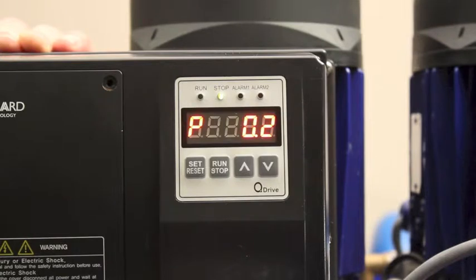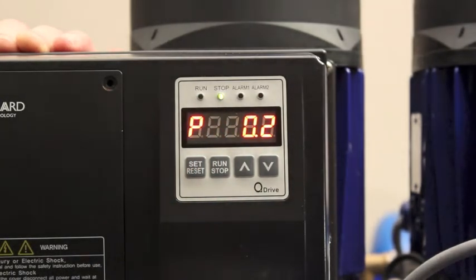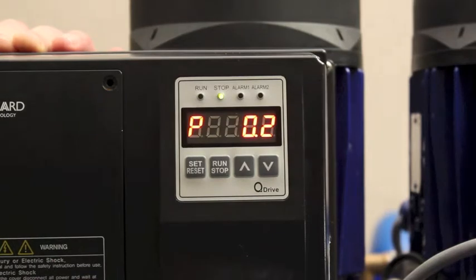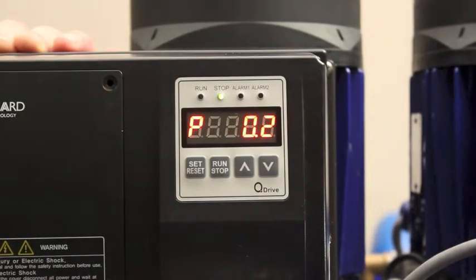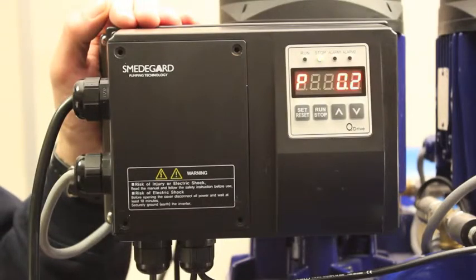Firstly, it is necessary to put the Flex Drive into stop mode, displayed by the green stop LED being lit up. The Flex Drive can be put into stop mode in a number of ways. These are firstly by pressing the Run Stop button on the Flex Drive. Secondly, by disabling the pump at the boiler house control panel, or thirdly by removal of the wires from terminals P1 and CG or Run and CG. It is important to take care when removing the wires. Ensure that the power is turned off and the unit is left for 5 minutes prior to exposing the electrical internals.